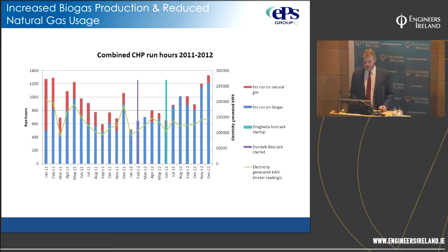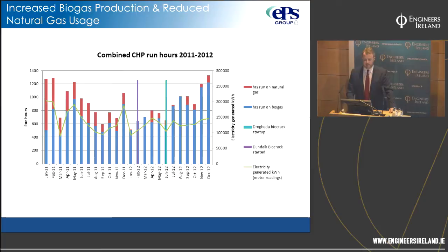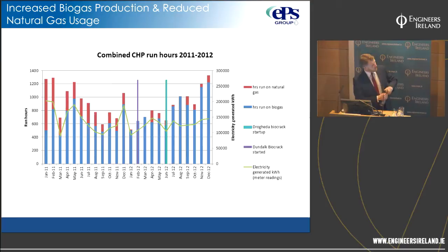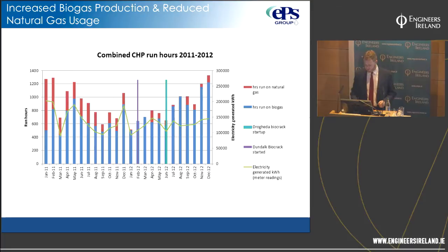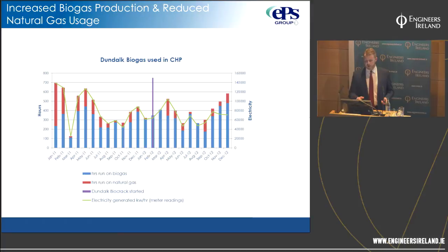Looking at the combined CHP run hours from 2011 onwards, you can see Dundalk coming online and then the Drogheda CHP following. What's notable is that not only has overall usage not changed drastically, but our reliance on natural gas has completely reduced. Breaking it down by site, Dundalk shows less natural gas use, though part of that is also due to being less wasteful than before we entered the trial.